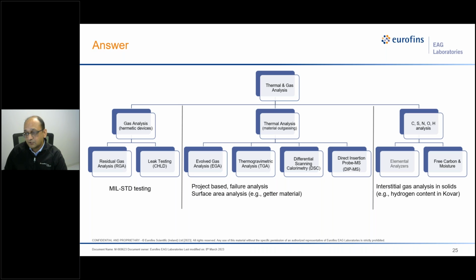The other segment of the thermal and gas analysis is related to the carbon, sulfur, nitrogen, oxygen, and hydrogen analysis. This is mainly done for solids and powders. A good example for this community could be if you are interested in knowing the hydrogen content in Kovar material, then these methods can be used, and the detection limit is exceptionally good here. We can measure hydrogen in the range of 2 to 5 ppm in a solid, and that capability makes a very strong base for doing anything related to gas analysis. Not only the final product, but if you have a failure analysis, or you want to qualify the epoxy that you are going to use in your next product, that can be done at this location.